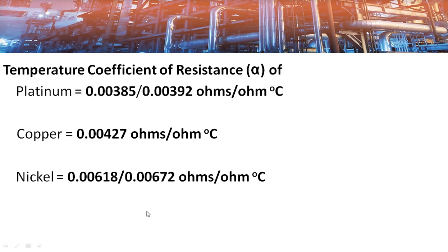Here you can see the temperature coefficient of resistance alpha values for different metals. The higher the value, the higher the sensitivity of the RTD. For platinum, there are two values: 0.00385, used for industrial applications, and 0.00392, used for lab applications where high accuracy is required. You can also see the alpha values for copper and nickel, and RTDs with other alpha values are also available in the market.